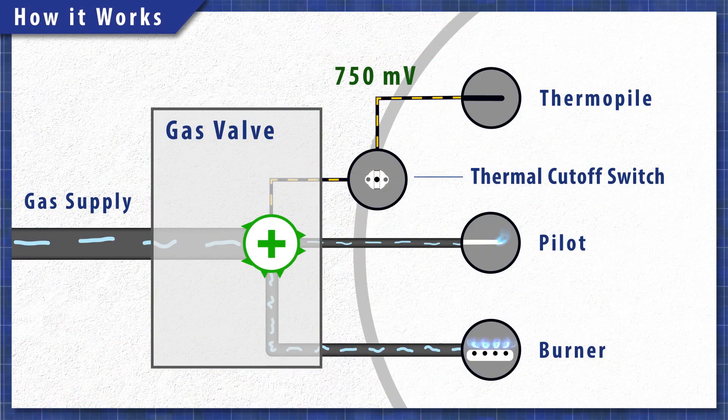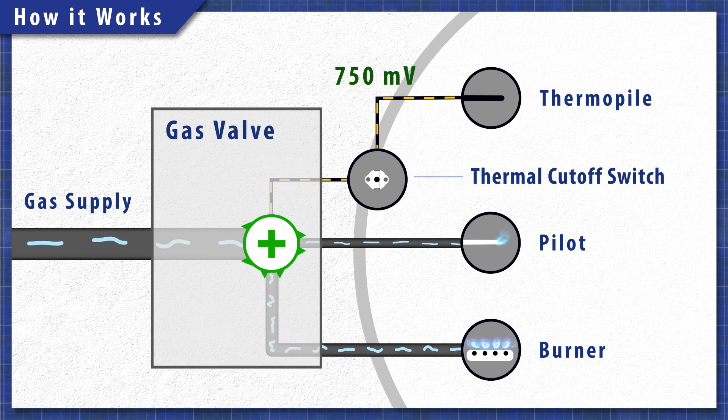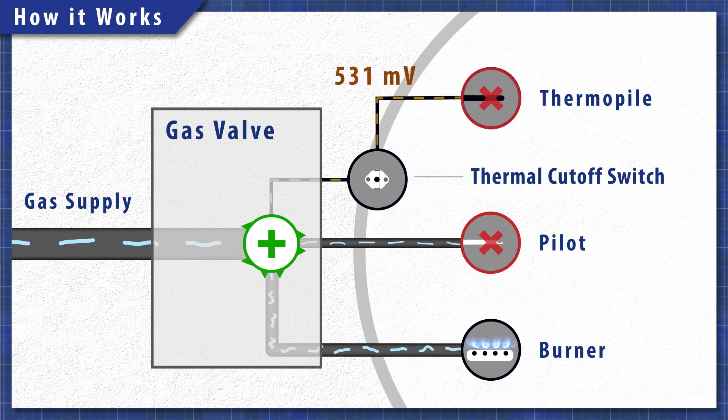The thermopile also acts as a safety switch. If the pilot light goes out, then the thermopile will cool down. The voltage will drop and the gas valve will shut off. This prevents unburnt gas from being released into your home.